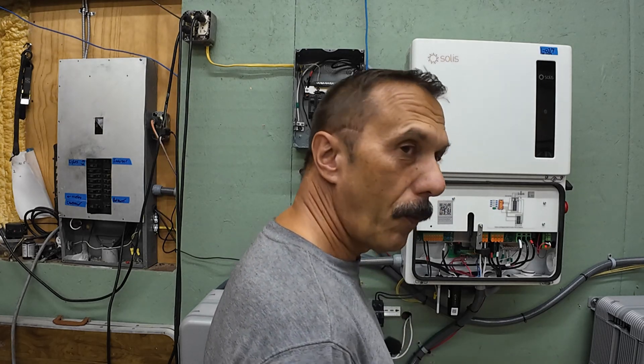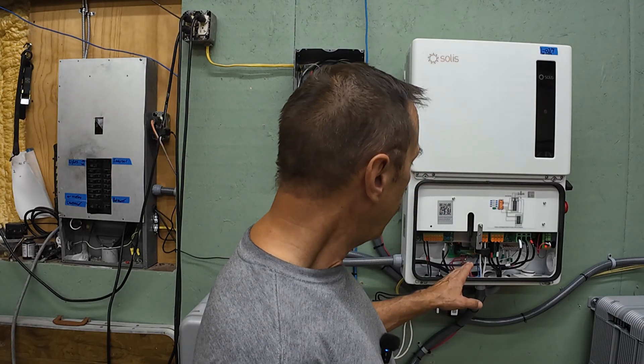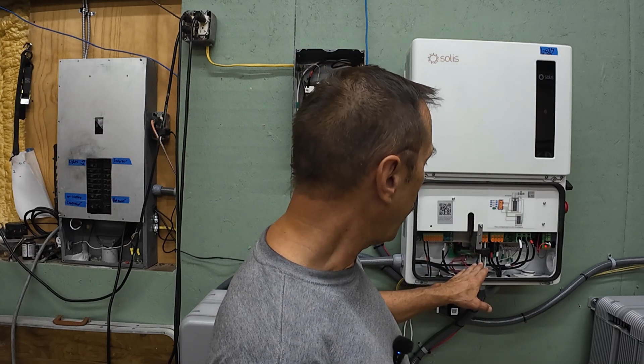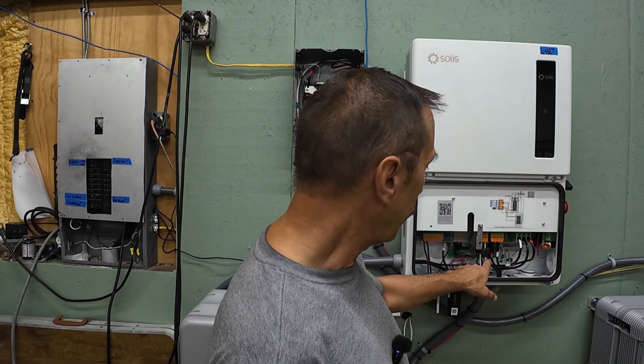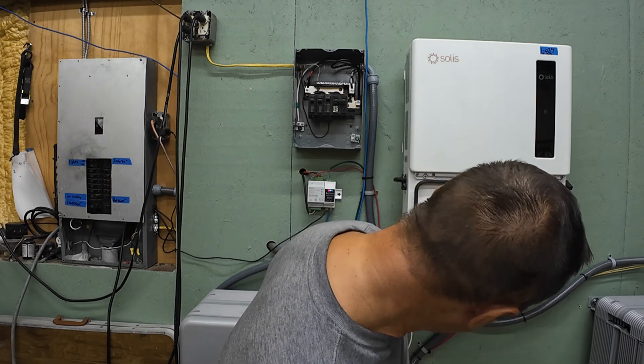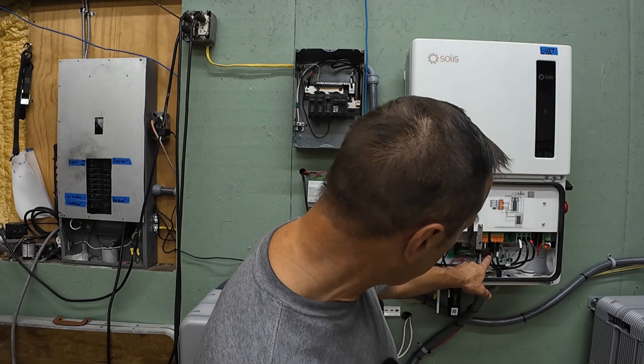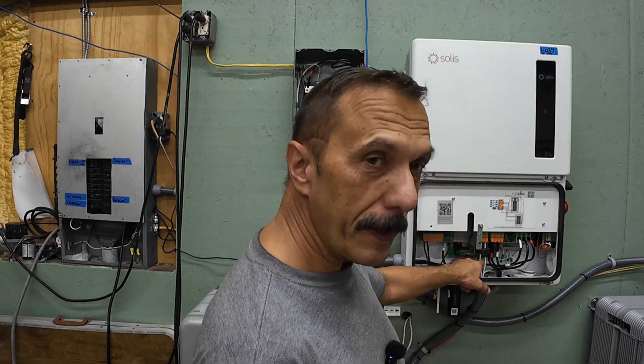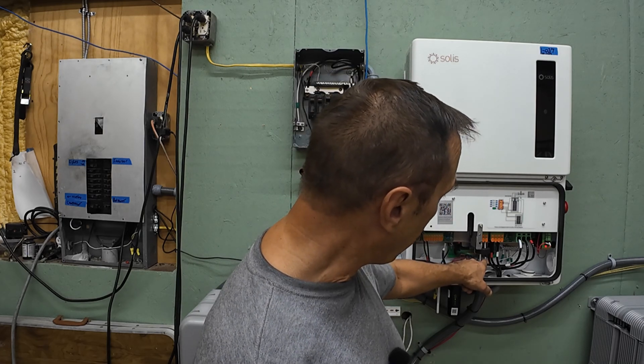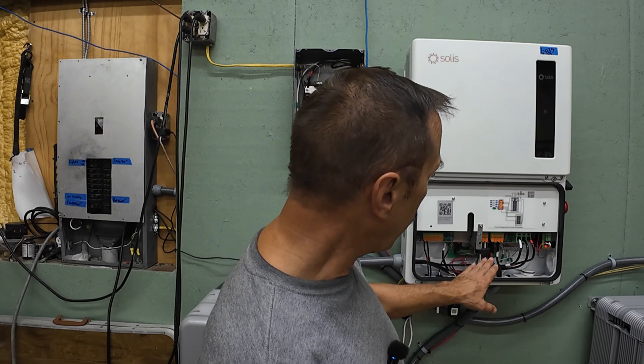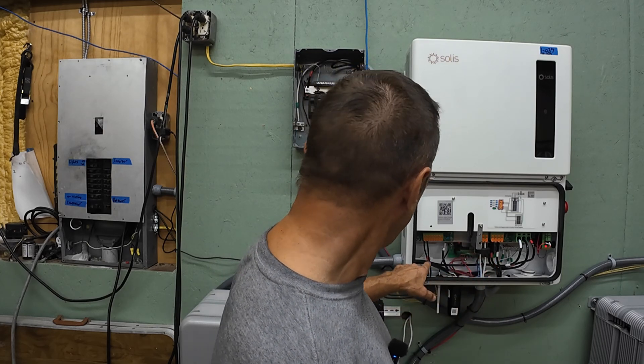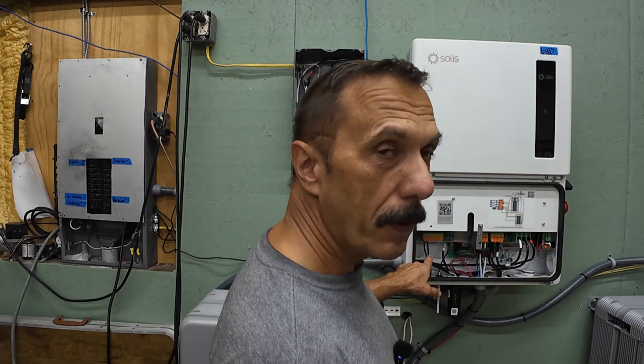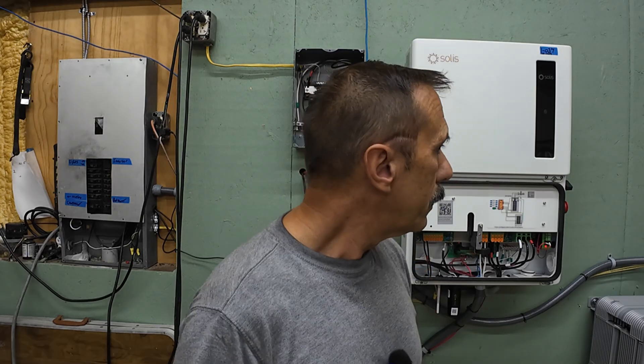When you're wiring up the battery, make sure you do a polarity check and label the cables. You can't see it here because underneath this ferrite core, but I've got the positive. I've got red tape on the positive and black tape on the negative. So, before you go connecting any DC source, that applies to the PV also. Make sure you know what polarity is going where.